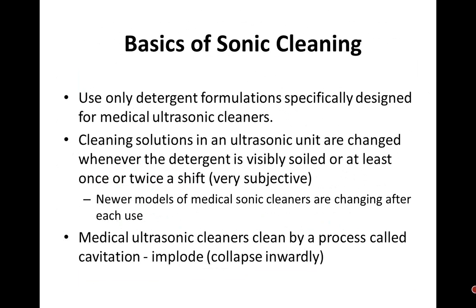And this is very important. As many people as we have right here today on this webinar, subjectively, we could all say that that bath looks dirty or it doesn't. The more soil or bioburden you have in that bath, that begins to impede the cavitation and the cleaning power. And many of the new models are changing after every use. And I hear this question, well, Steve, my sonic cycle is longer. Well, the total could be longer in the sense that you're starting with a new bath, it's degassing, it's draining, and so on, where you're just used to putting it in and running it for the 15, 10, 20 minutes or whatever it is. So that total cycle time, from when you put it in to the very end, might be longer, but again, it's giving you a fresh bath.